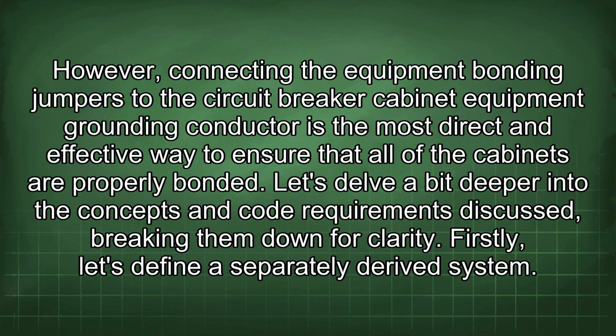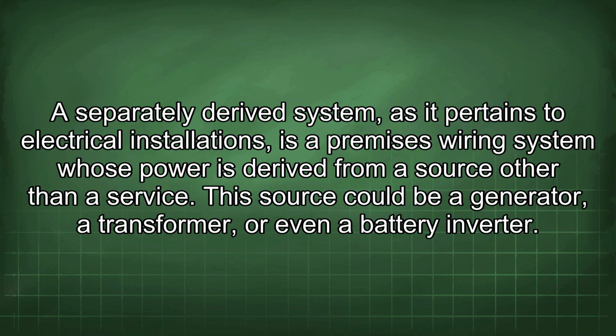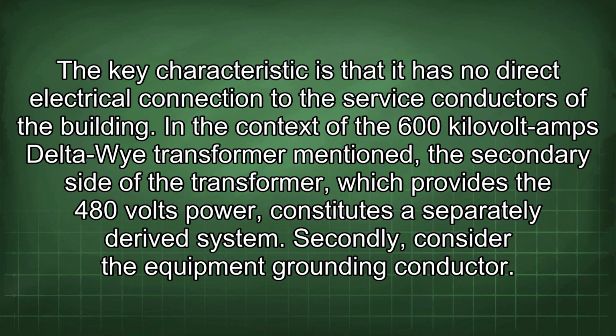Let's delve a bit deeper into the concepts and code requirements discussed, breaking them down for clarity. Firstly, let's define a separately derived system. A separately derived system, as it pertains to electrical installations, is a premises wiring system whose power is derived from a source other than a service. This source could be a generator, a transformer, or even a battery inverter. The key characteristic is that it has no direct electrical connection to the service conductors of the building.